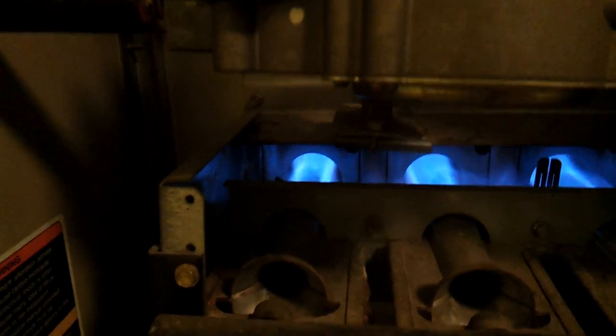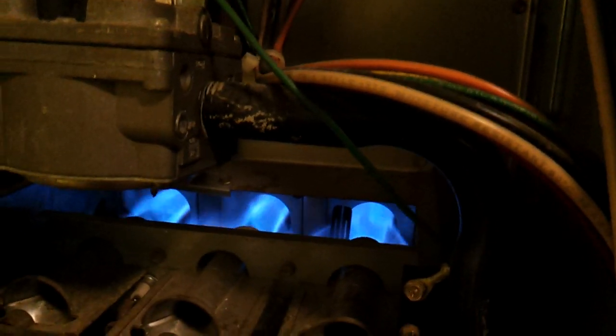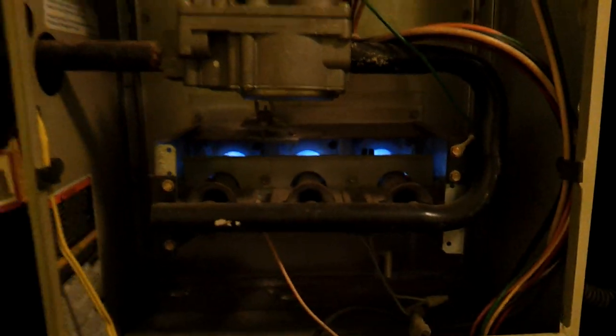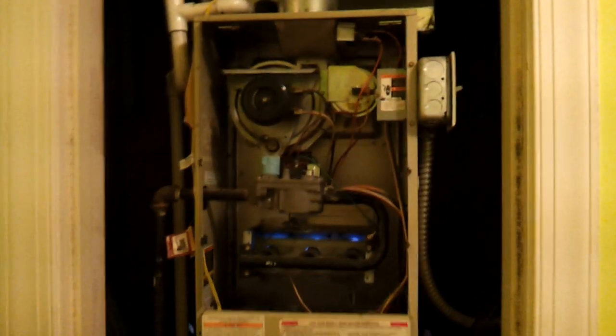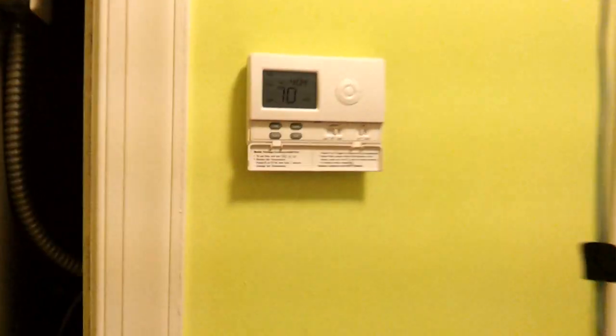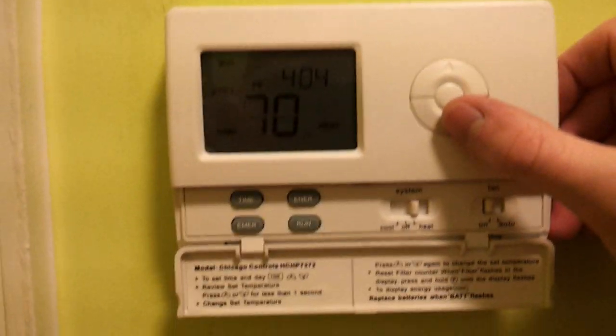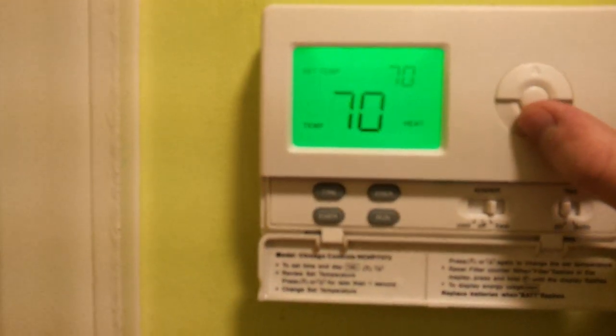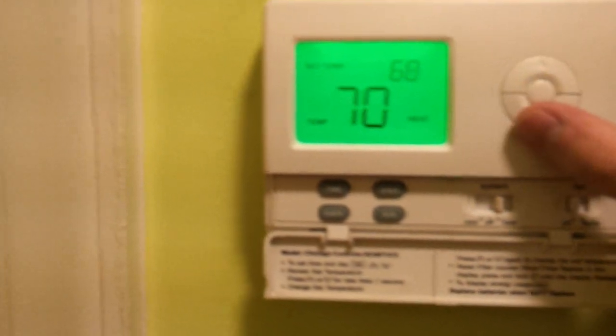Here's that flame sensor wire. That goes back to the control board, and the flame's actually inside the little flame sensor rod right there. So if the flames were to go out, it would shut off gas to the unit immediately. But yeah, that's the Carrier Weathermaker 8000 furnace, and I'll go ahead and cease operations here because it's actually pretty warm outside. So we'll go ahead and set that back down to about 68. And you'll see it shut off.